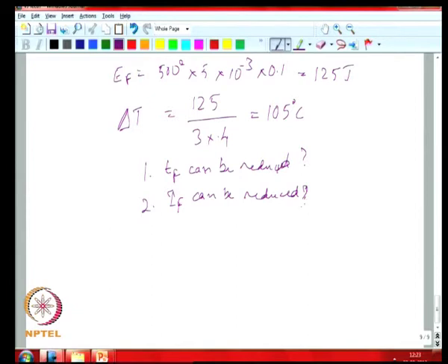The other thing that you could do, which might be more directly under control, is maybe instead of a 12 gauge wire, you use a thicker wire, you might choose a 10 gauge wire, okay, because you saw that your I squared T goes as A squared. Now, using the thicker wire will reduce the temperature to which it would go during the fault duration.